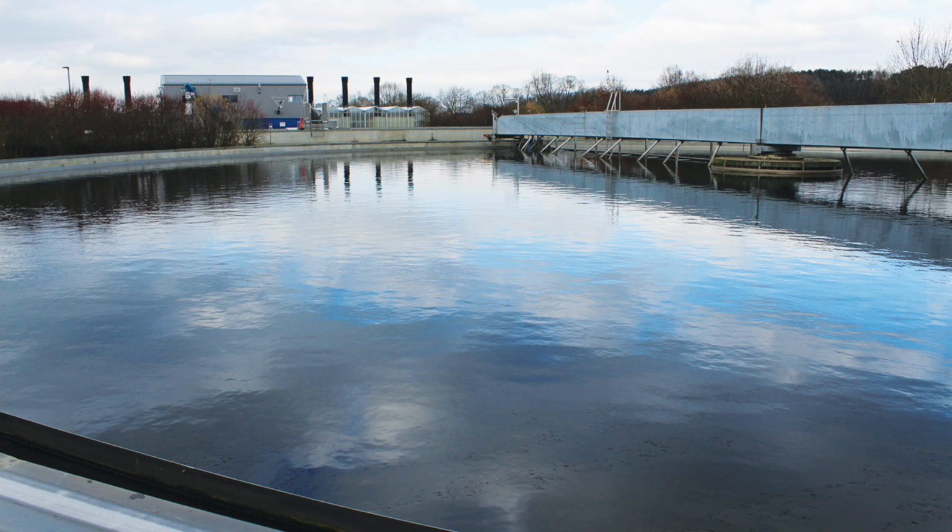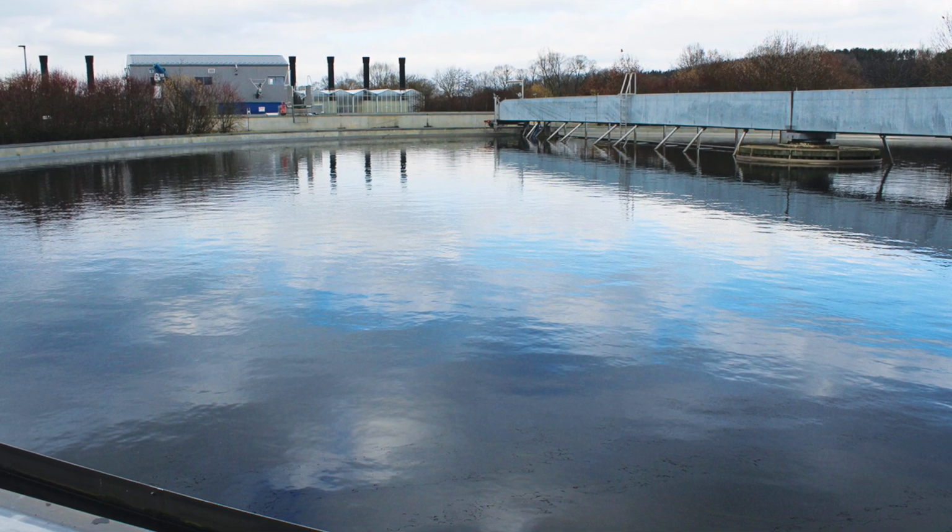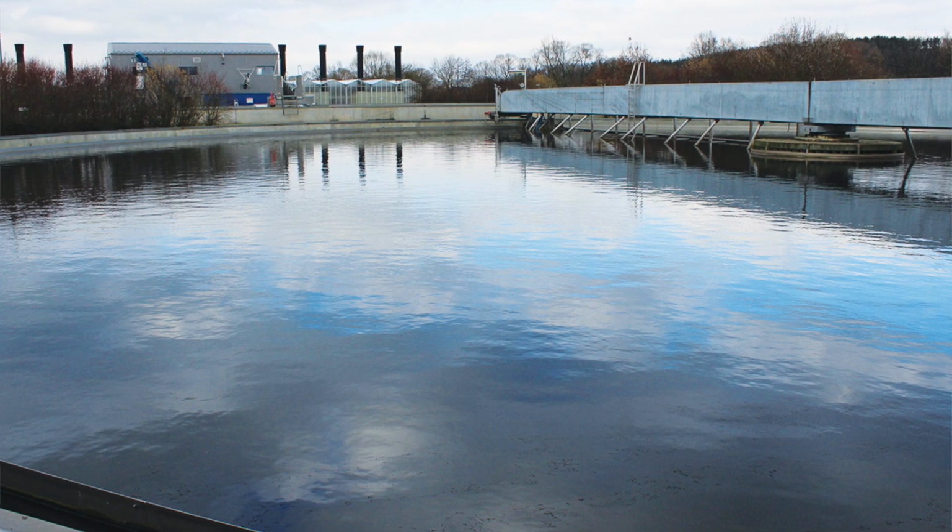The second example that comes to mind is a different wastewater plant in Bayreuth, Germany. Bauer actually did a couple things there to help them save money. The first was to create an above water aeration drive, and they coupled that with utilizing VFDs to really optimize how those motors ran efficiently. Secondly, Bauer worked with the chief machine operator, and they were actually able to downsize the eccentric screw pumps from what was a 15 kilowatt IE3 asynchronous motor to a 5.5 kilowatt permanent magnet motor. So almost one third the size.